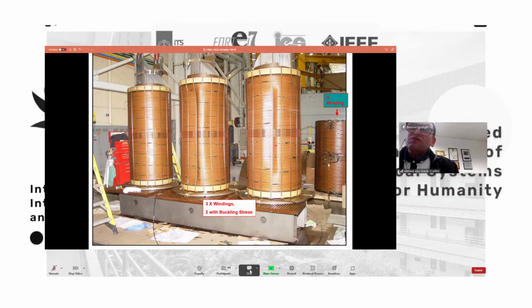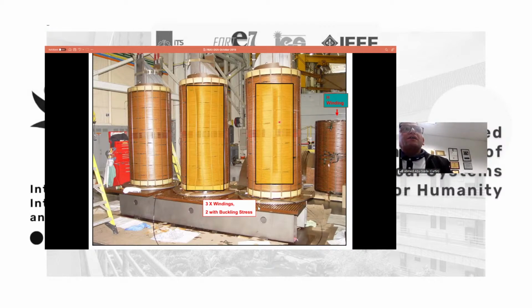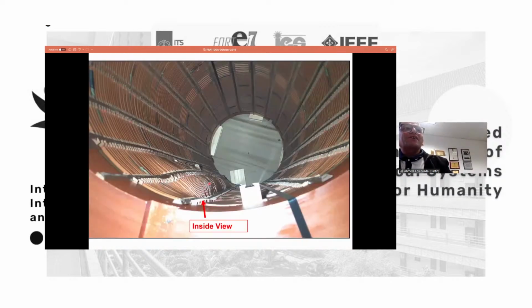You know, when we have a short circuit fault, the short circuit current can interact with the leakage flux, phi, and cause electromechanical force that may cause the winding to move down, or to have buckling like this, forced buckling. You can see the buckling here. That's a huge force. If you don't see it from there, I highlighted it here, but you can see it from inside. That's the inside view. Again, with such a fault, the transformer will look normal. You won't see that. But if you don't notice it, you may lose your transformer, and it may lead to catastrophic fire. So that's the problem of such faults.